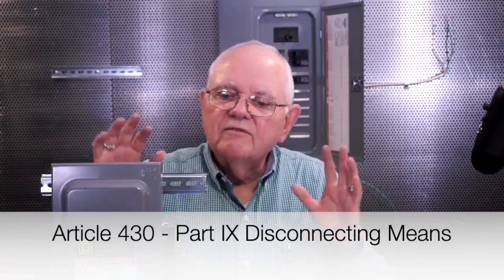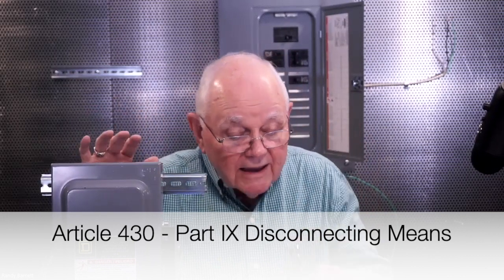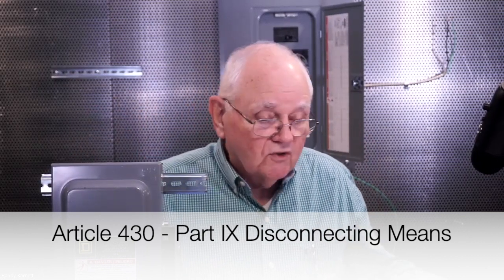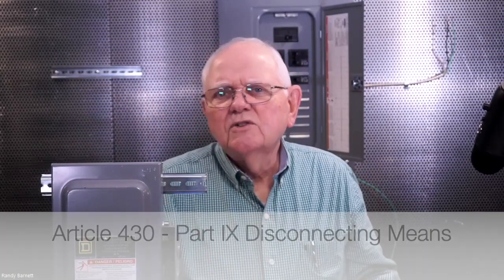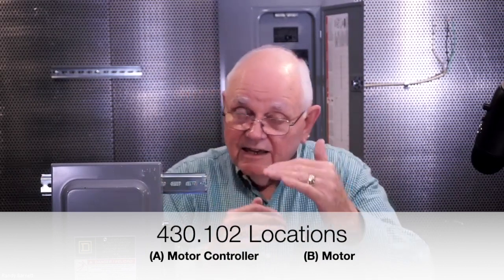Let's take a look at Article 430, Part 9. Part 9 says that I have to have a disconnecting means capable of disconnecting motors and controllers from the circuit. So let's go take a look at 430.102 and see what the code has to say about disconnecting means for motors. In my code book, that's page 356 in the 2023 code. 430.102 is divided into two sections. Subsection A is for motor controls and subsection B is for the motor itself.